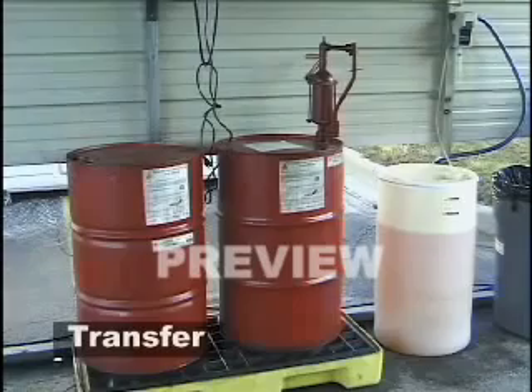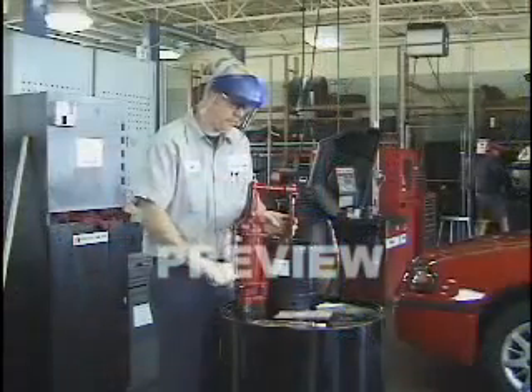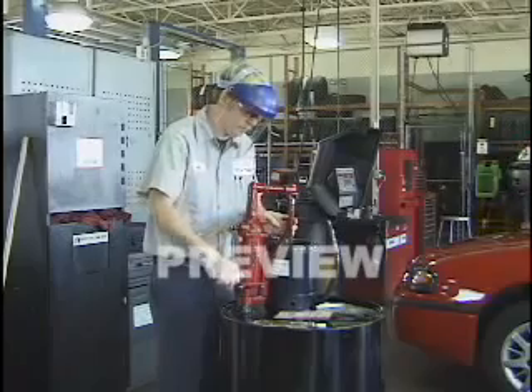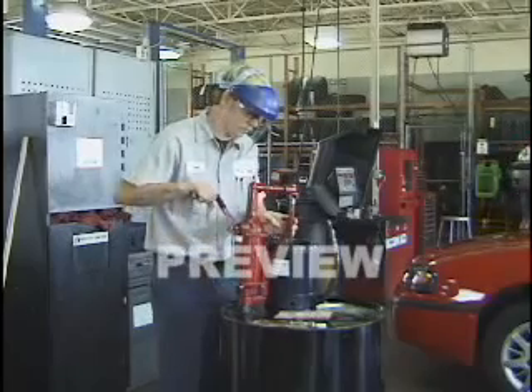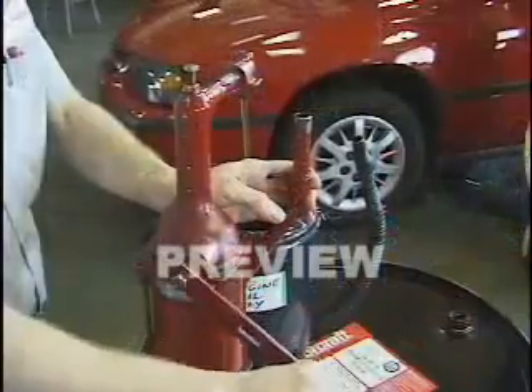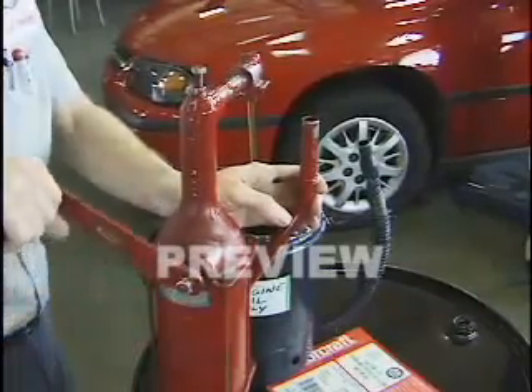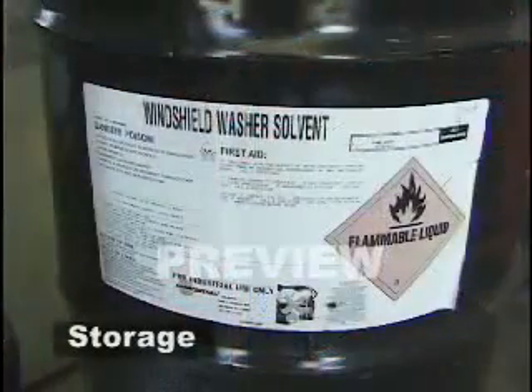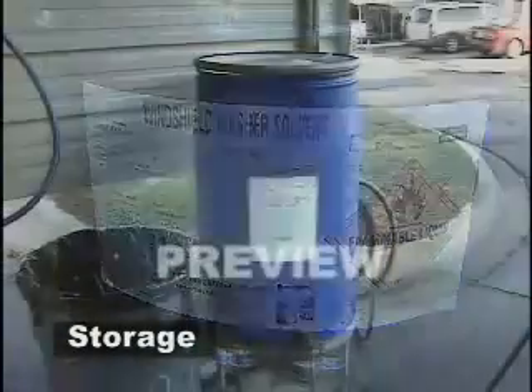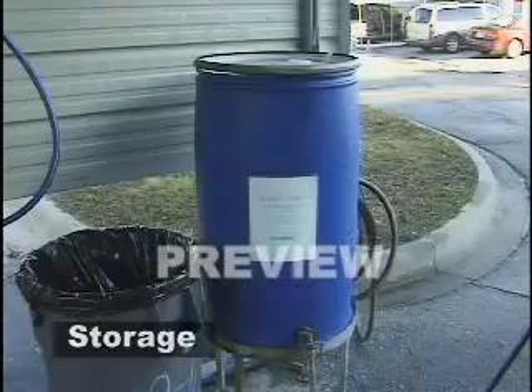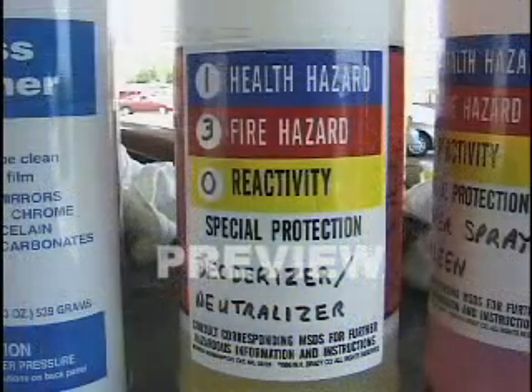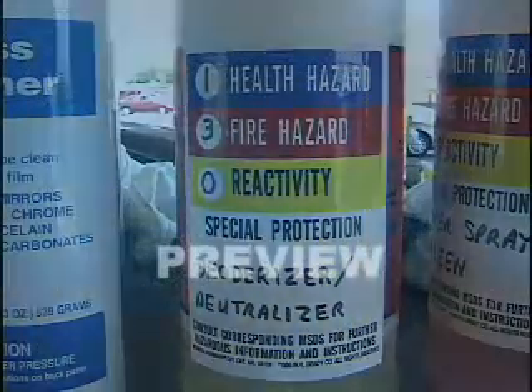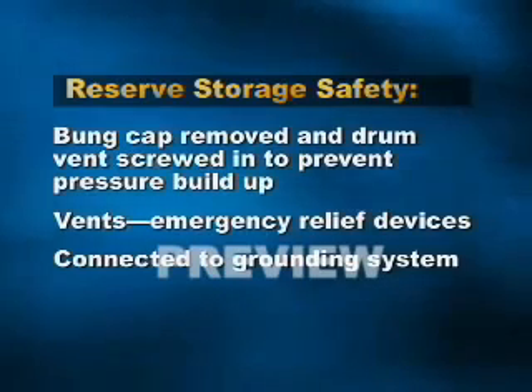Transfer of flammable liquids refers to their removal from storage to the places where they will be used. Liquids can be dispensed from drums by two methods: gravity flow for drums stored horizontally and pump method for drums stored vertically. The typical workplace stores flammable liquids in two ways: reserve storage in drums and storage in small quantities for use at workstations.